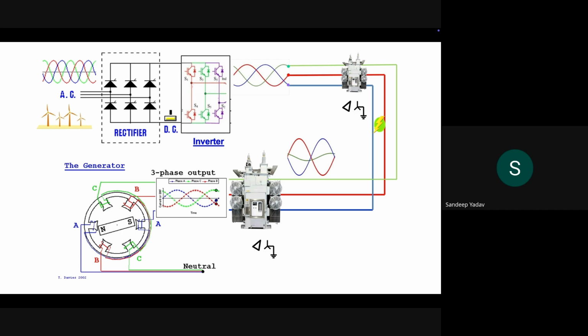What will be the ride-through requirements, both in terms of low voltage and high voltage, and how much reactive power it will consume or at what power factor it will run. All of these things are defined in the grid codes, and all the generators which are connected at the grid point, the point of interconnection, and all these IPPs are bound to follow that grid code. So in every country we have these grid codes in place, and when a generator is connected for the first time, all these requirements are checked through the models as well as at the site. At first-time interconnection, or when the first-time energization clearance is given, all these requirements are verified.